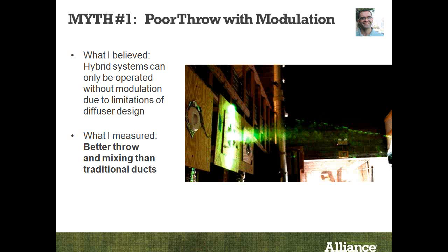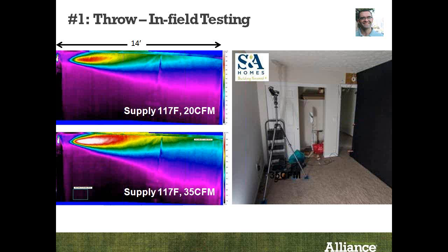And the reason for this, I believe, is related to the openness of the diffuser. It's basically a round 2-inch for Unico, and it's a 2.5-inch for other systems that we've looked at. And there's nothing cutting the air coming out of it, so the air kind of sticks together and penetrates very deeply into the room. So here's a test that Andrew completed at the Pittsburgh Lab House.